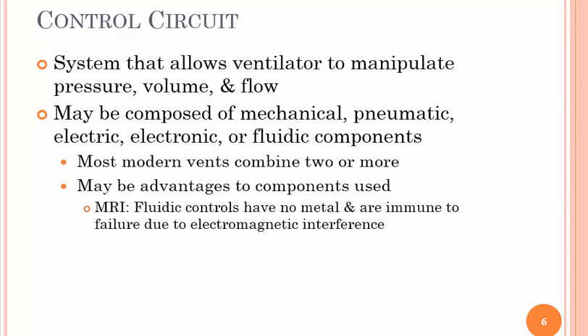The control circuit is the first topic. We're not talking about the breathing circuit here — this is like the electronic circuit inside the ventilator. It is a system that allows the ventilator to manipulate pressure, volume, and flow. They may be composed of mechanical, pneumatic, electric, electronic, or fluidic controls.